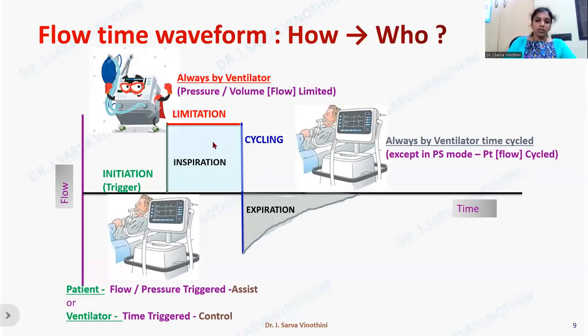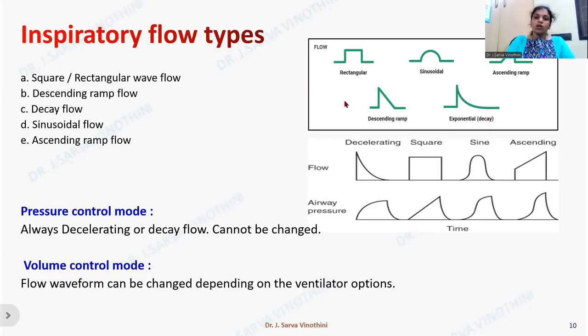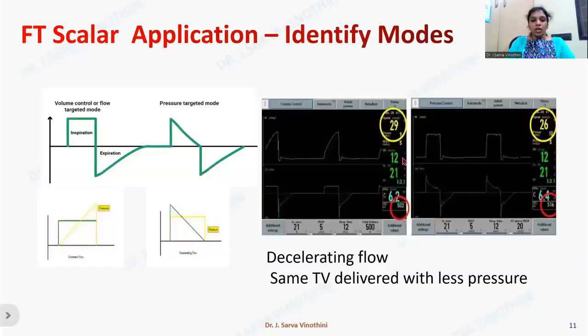The inspiratory flow can follow various patterns: rectangular, sinusoidal, ascending ramp, descending ramp, or exponential. It is usually rectangular in volume control mode, but can take any pattern. In pressure control mode, it should always be a descending ramp or exponential flow pattern. In normal spontaneous breathing, we see a sinusoidal flow pattern. So pressure control mode always has a descending ramp or exponential pattern, whereas volume control mode can have any kind of flow pattern.